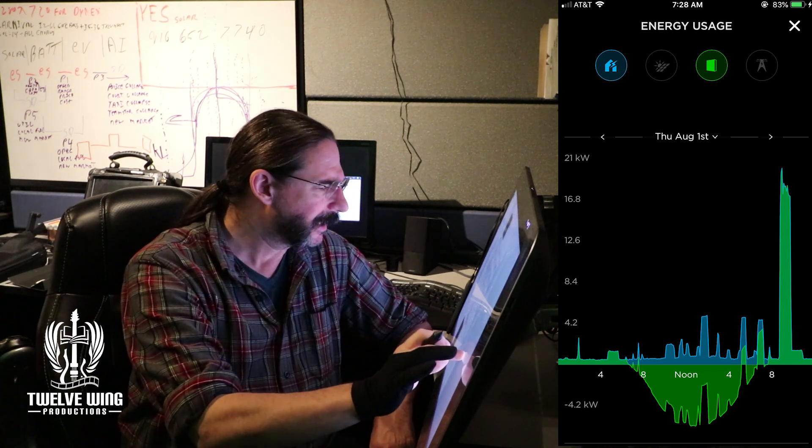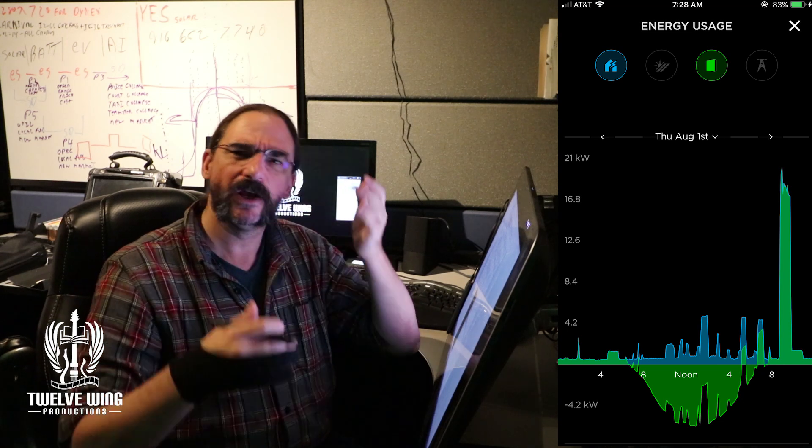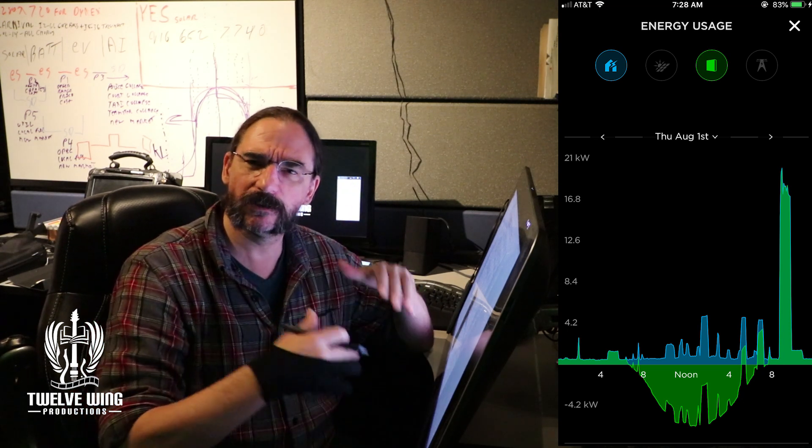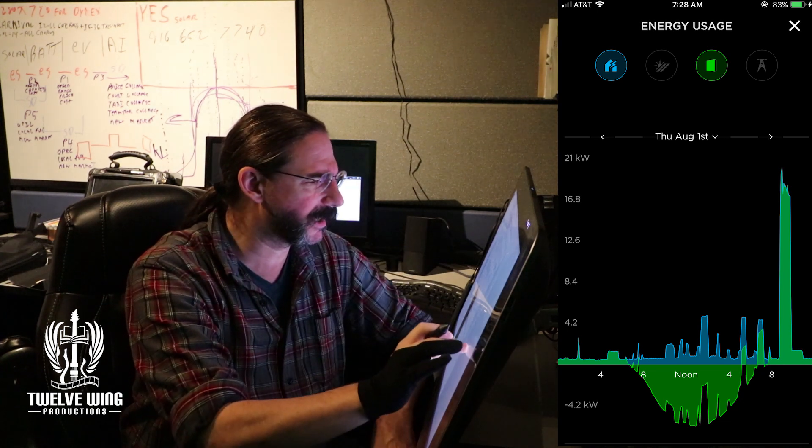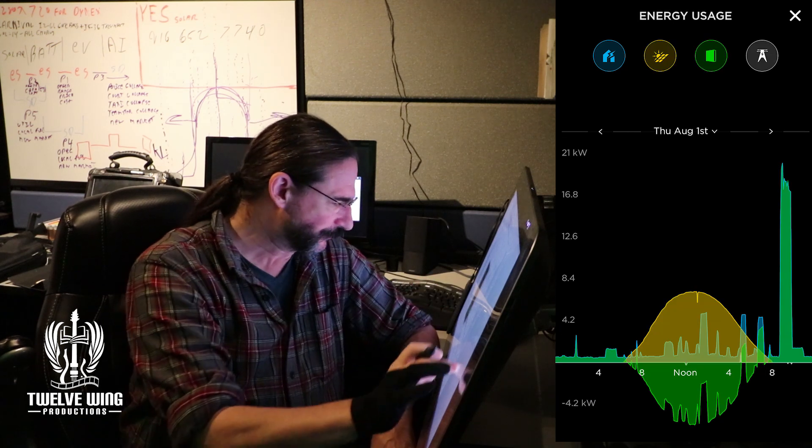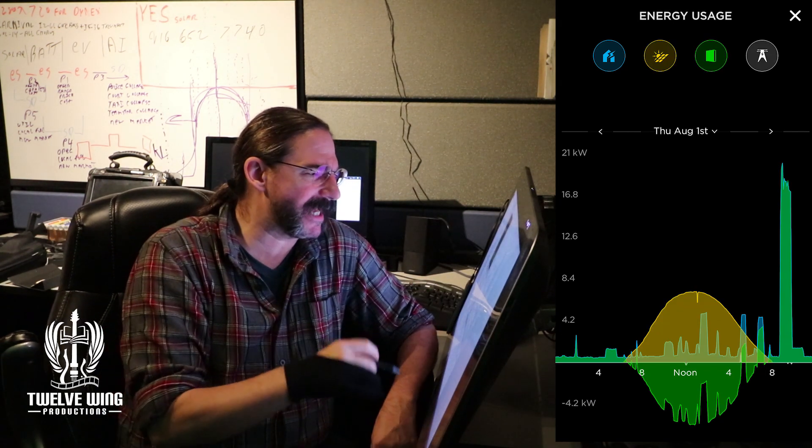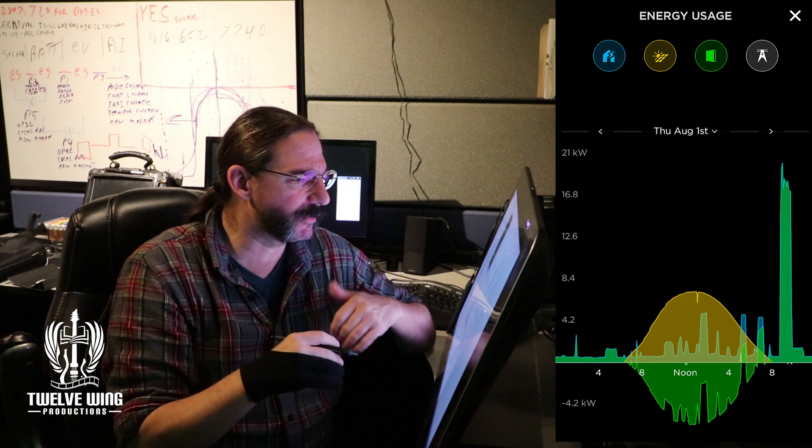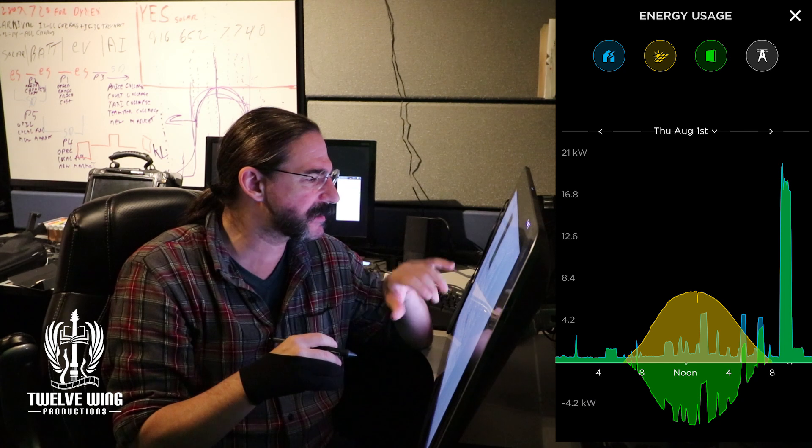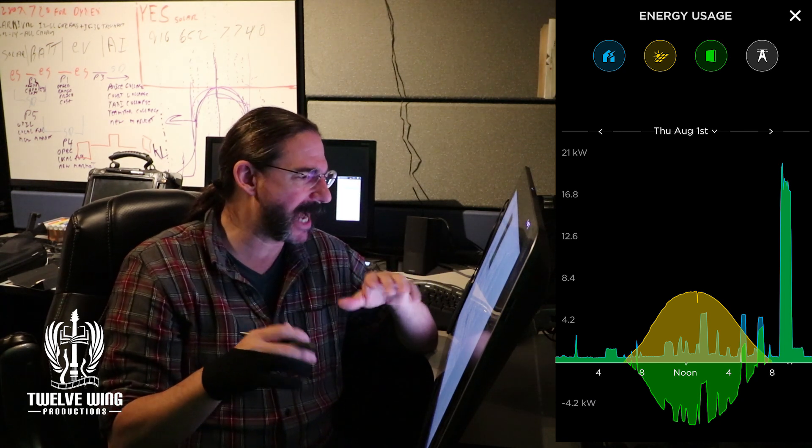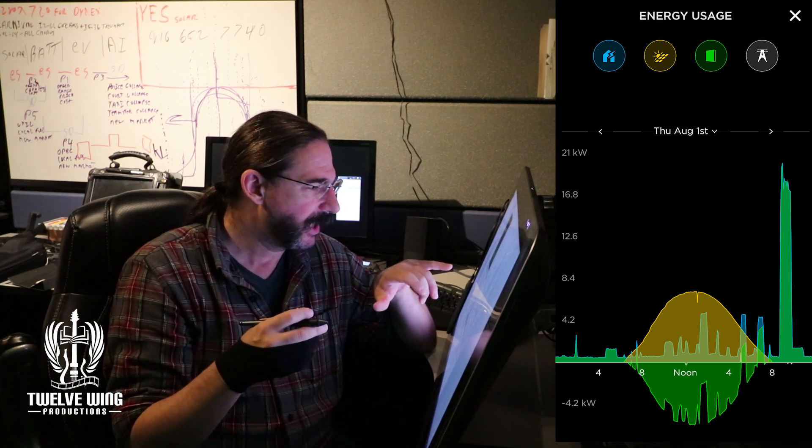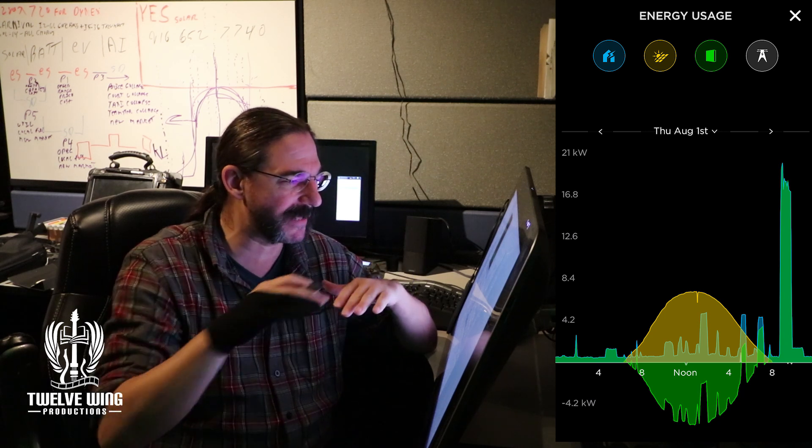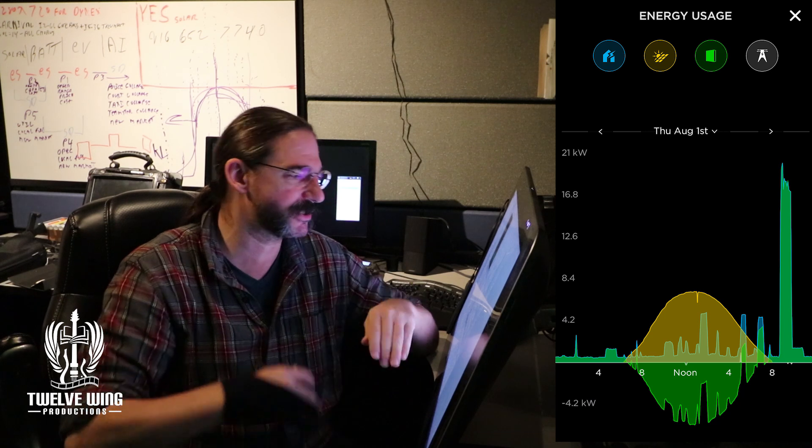And so with an understanding of all of this, now let's go ahead and look at the total combined graph and see what that can tell us. It's got some interesting details there. Chris had specifically asked what caused that blue peaking up above the yellow and the green that you see on the peaks at 5 and 7 pm. Our clue there is actually on that 7 pm spike. It's really easy to see there. If you look closely at the spike, you'll notice it's got a flat top to it. This is obviously a load from our air conditioning system.